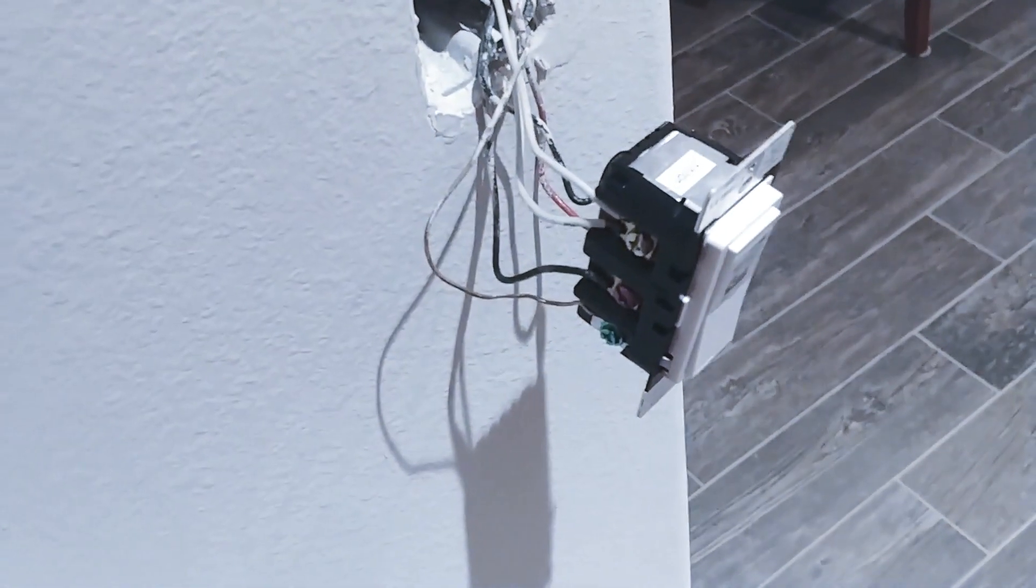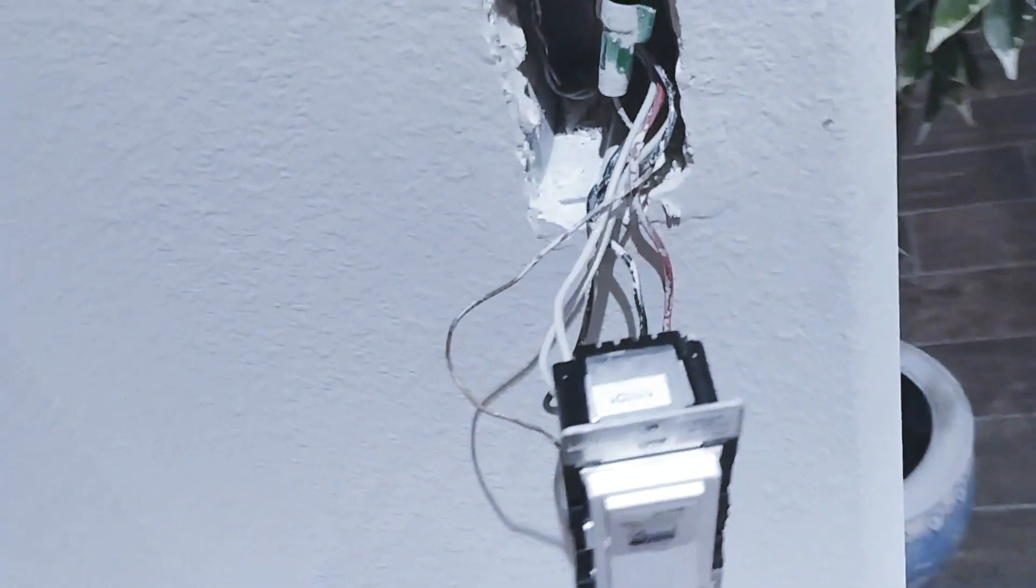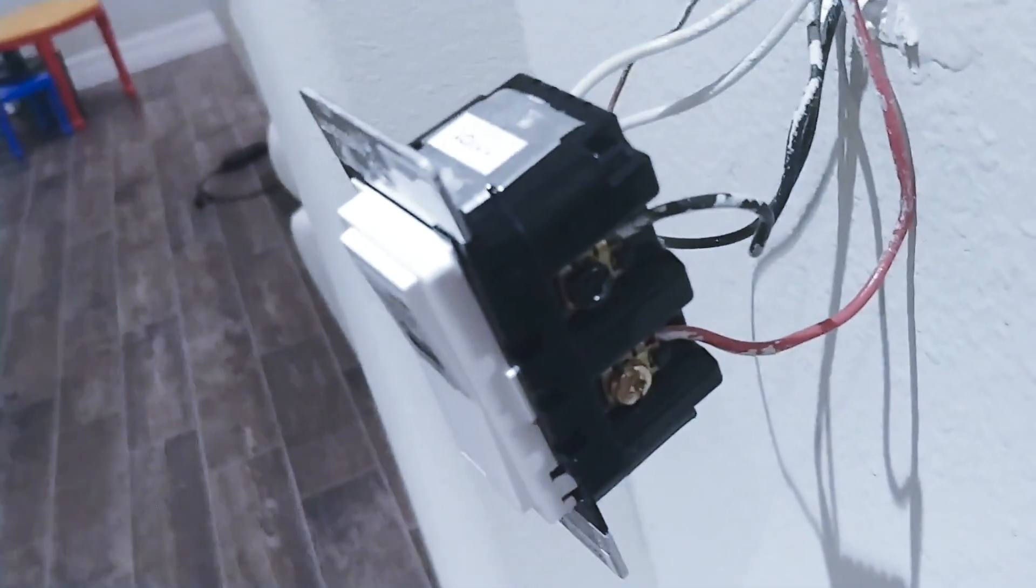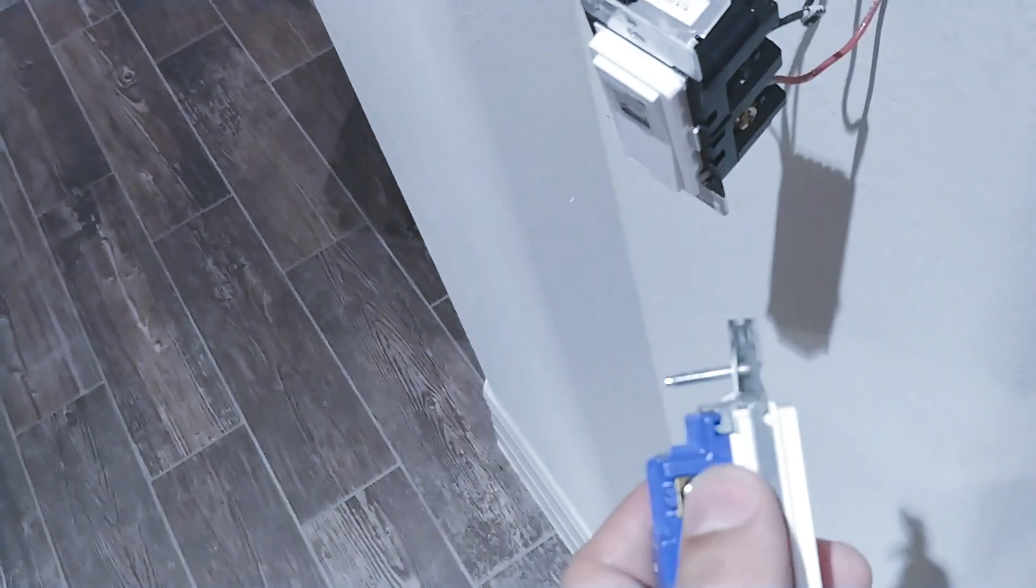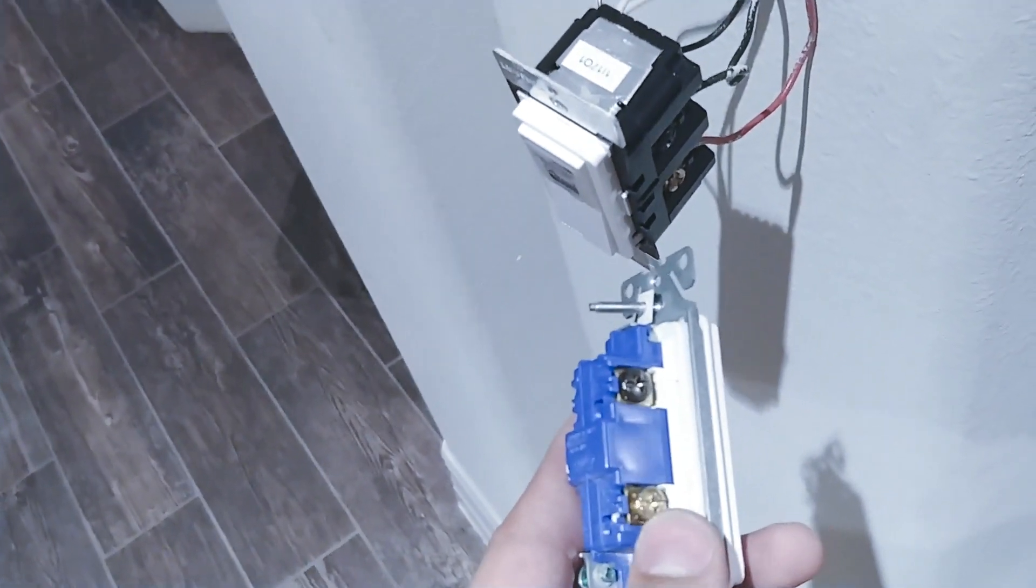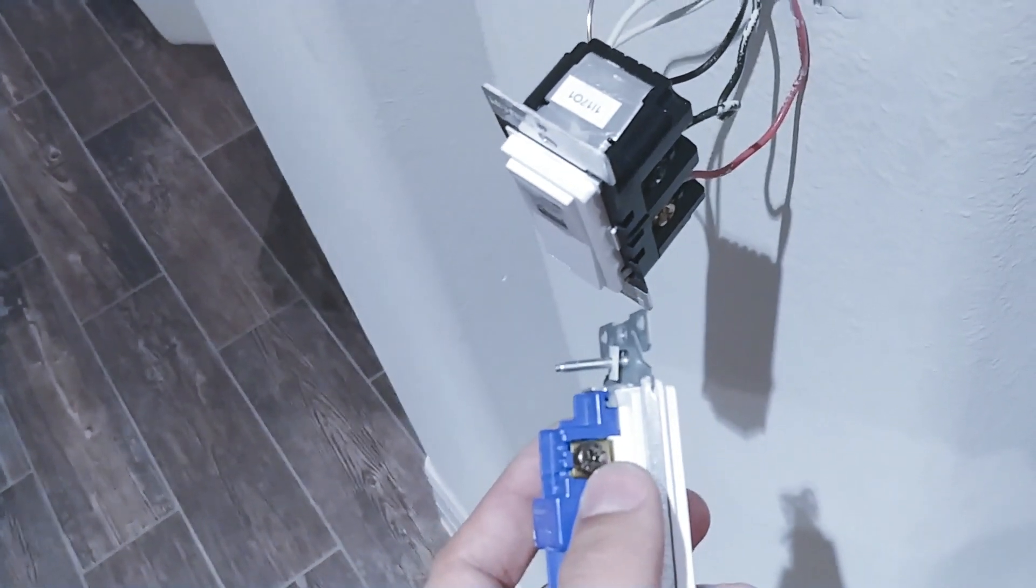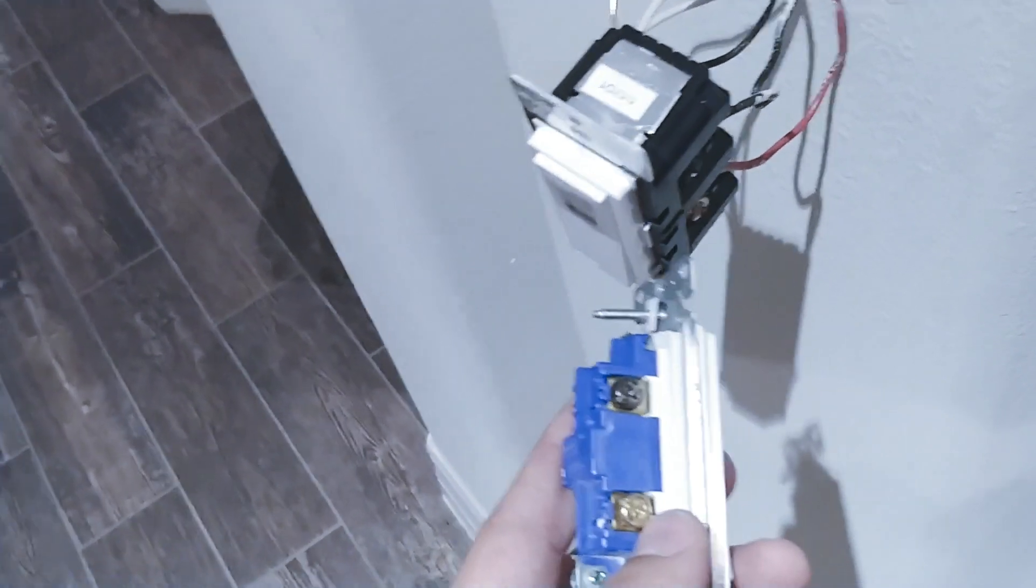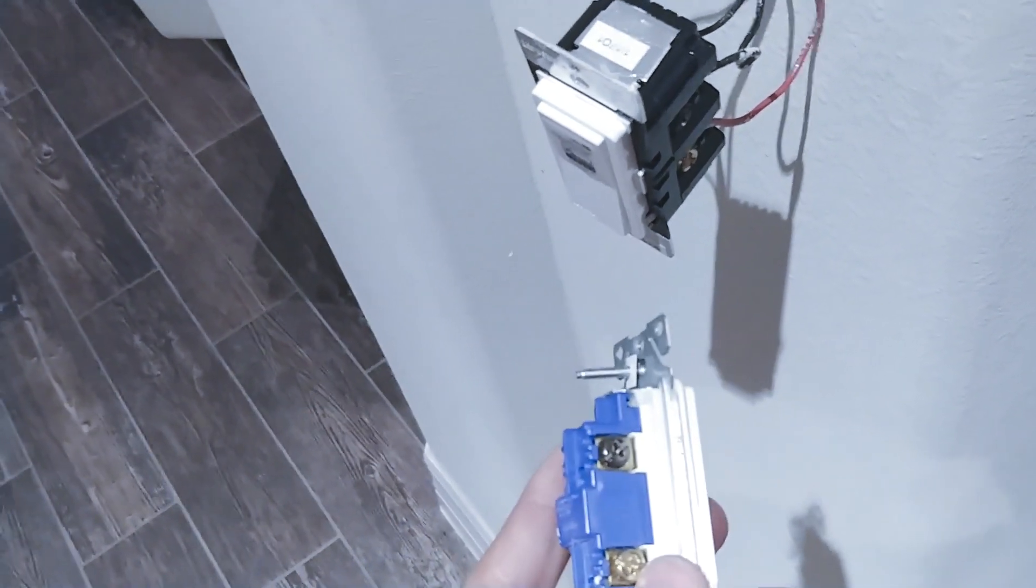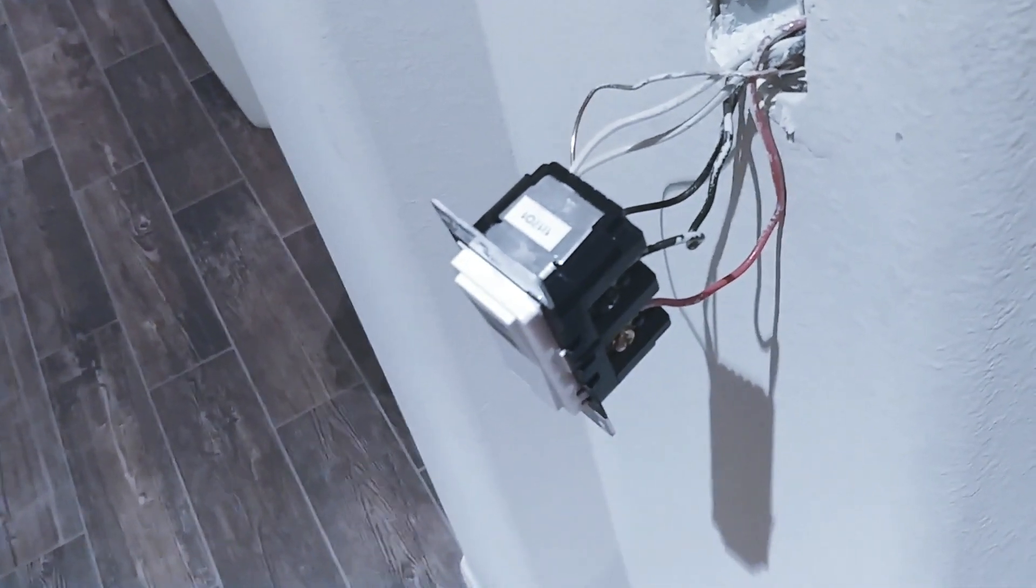Okay the wiring is complete and you can see it works. So there is one correction I want to make from the last video. I did mention that the black wire that was going to the black screw on the switch down here was the one going to the load and this was the one going to the line. That was actually incorrect. The black wire was actually going to the line and the brass wire was going to the load. I have to make that correction because when I hooked this up it didn't work and when I swapped those wires it did work.